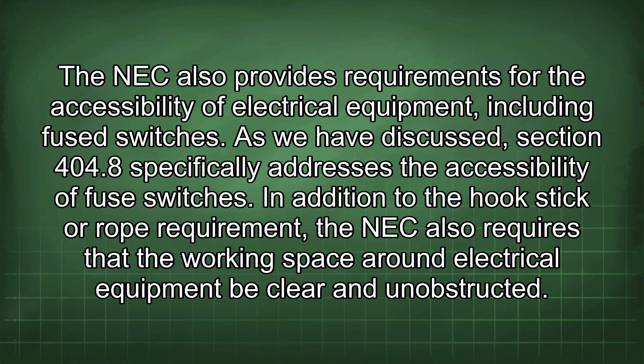In addition to the hook stick or rope requirement, the NEC also requires that the working space around electrical equipment be clear and unobstructed, to ensure workers have enough room to safely perform maintenance or repairs. The working space must be at least 3 feet deep, 30 inches wide, and 6 feet 6 inches high. The NEC also requires adequate lighting in the working space, sufficient to allow workers to safely see what they are doing.